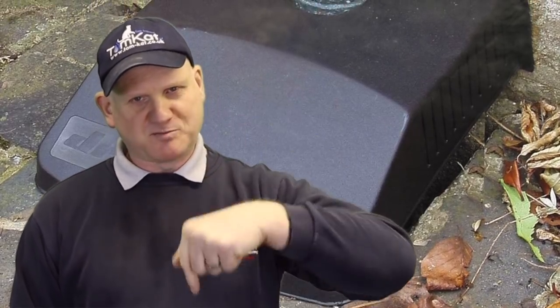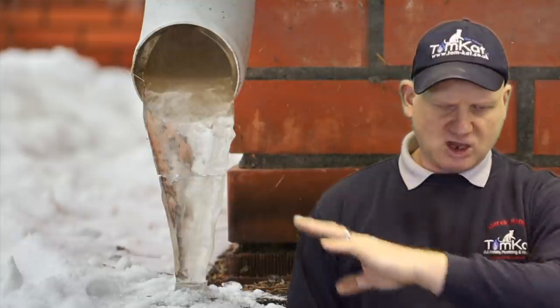How many of you do that then? It also needs to be terminated below the grid, but above the water level, and cut to a 45 degree angle, and have a leaf and debris guard over the top of it now. And this is all to stop the chilling process, so freezing cold wind chill factor wind blowing across the top of the grid and freezing the outlets of the drain.